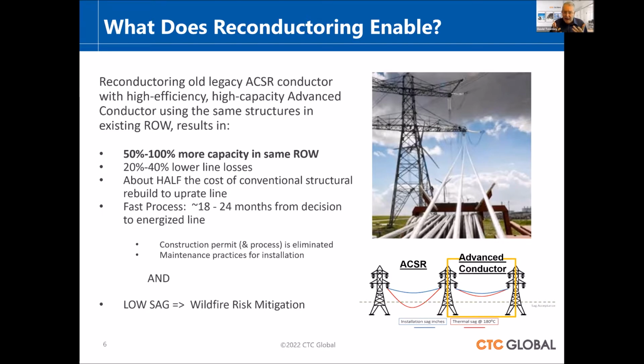And because you're not rebuilding the towers, it's at least half the cost of the conventional structural rebuild in order to upgrade that line. And again, because you're not rebuilding the structures, you don't need the environmental permitting, the construction permitting. All of that is gone. In fact, you're using maintenance type practices for installation, the same kind of practices you might use for rebuilding after a storm. And that enables you then to do a very fast process, because you don't need these permitting processes. You now can be in a 18-month, 24-month kind of max from the time you decide you're going to do it to the time you've installed and energized that line.